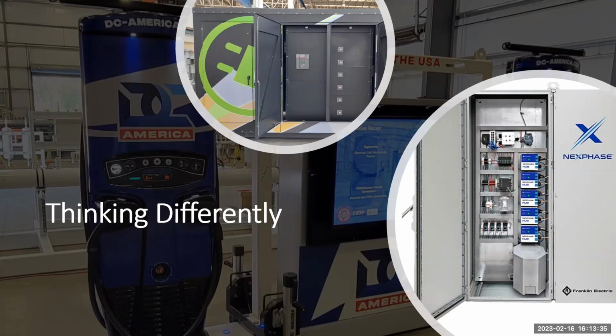At Virginia, we have combined at least 4 of the steps, leveraging our expertise in moving energy by combining medium voltage breakers, switchgear, transformers, a main breaker panel, and low voltage distribution, all into one single unit, assembled in the factory and shipped completely assembled. So complete plug and play - you connect primary and low voltage side, and you're ready to go, at a fraction of the footprint of the individual components. You're saving a lot of real estate, time, and pain because everything is integrated.